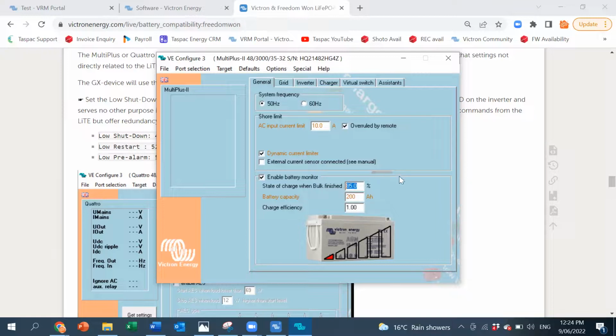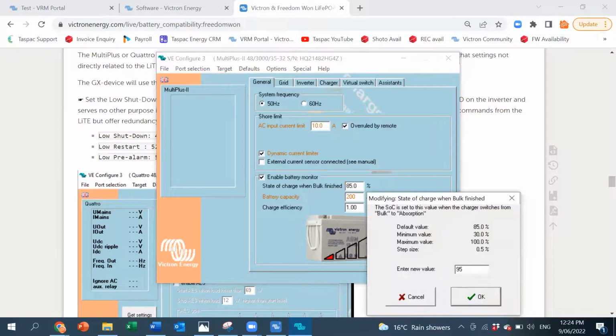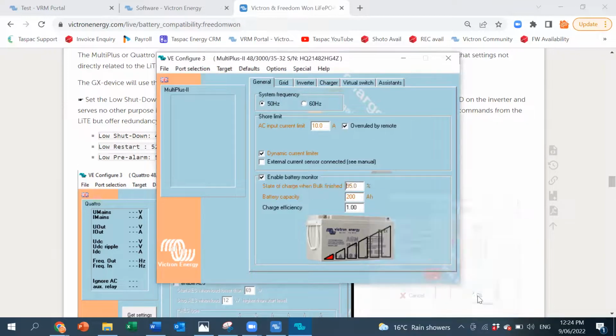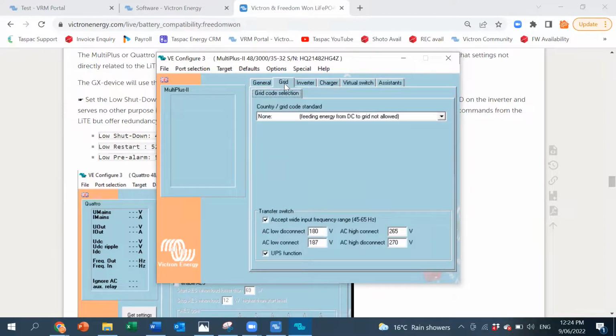The reason you do it lower is so that if there is a problem, the customer's going to see, oh, we've used a lot more of the battery today than what we normally have, and they might ring the installer and the installer will find out that there's a problem with the comms cable. 95, when the bulk is finished, it's pretty much 95% charged or even greater with lithium. Charge efficiency 1, that's fine. We go to the grid tab here. We don't have a grid, so we're not going to set a grid code. Just leave it as none.